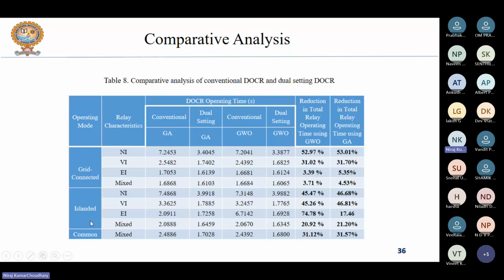For the grid connected mode and islanded mode, for conventional type of DOCR using GA and GWO, and for dual setting DOCRs, the results obtained using GA and GWO are shown, and accordingly the percentage reduction in the total operation time has been noted here. So you can appreciate the performance of the mixed inverse characteristics as well as the performance of the common optimal setting of the relay when you compare it with the conventional DOCRs using the NI, VI, and EI characteristics. The percentage reduction has been shown in this table.